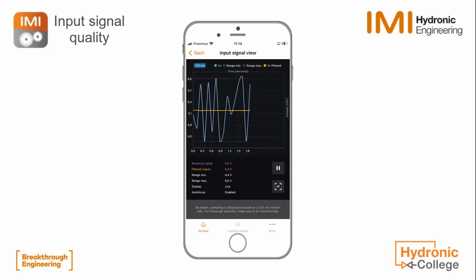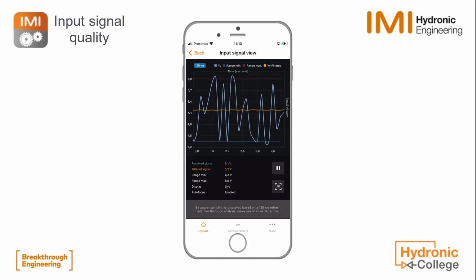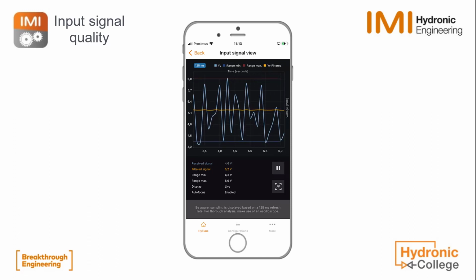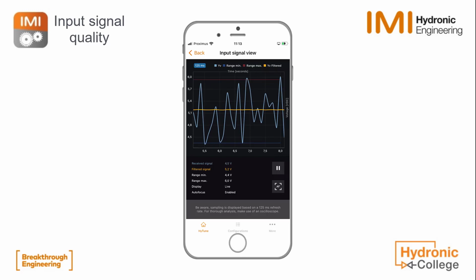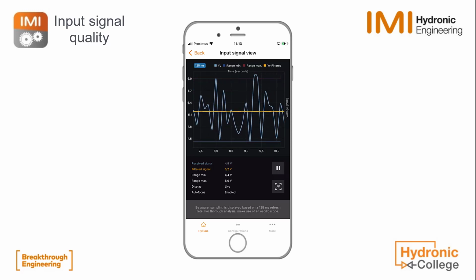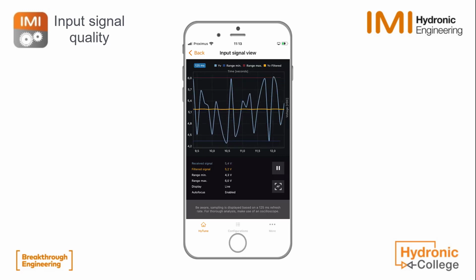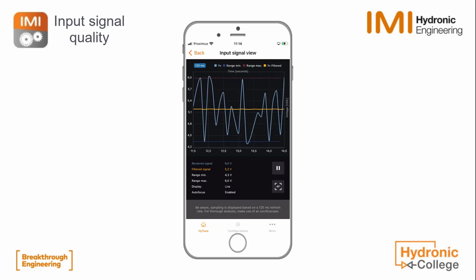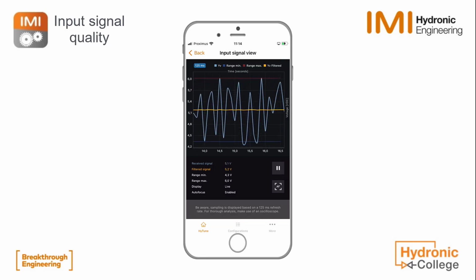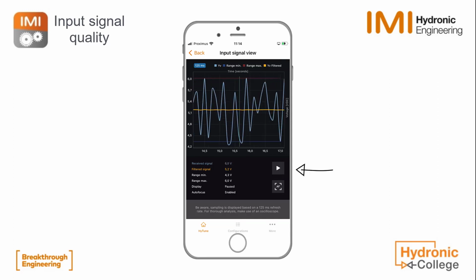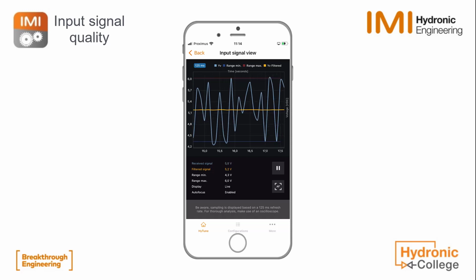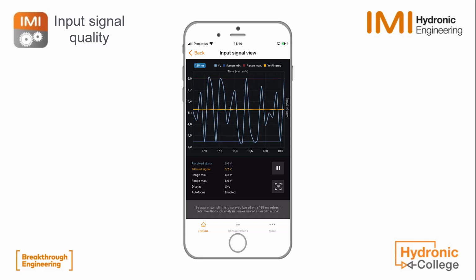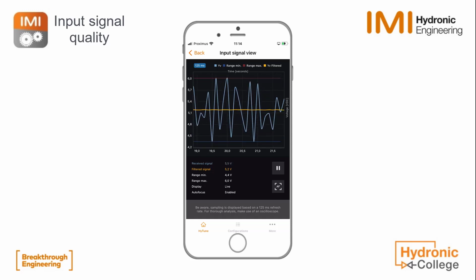Afterwards, voila, we click on input signal view and you see here what is happening. We have the blue line, which is the input signal. We have the range max and min, and the yellow line is the filtered input signal. We have the possibility to pause, so to freeze the view with the pause button and to see the full range from 0 to 10 volts, or the other way around.